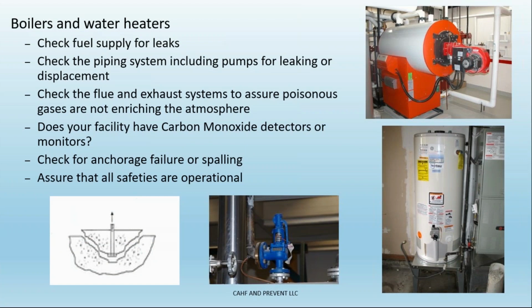Check your motor mounts on your pumps. Those are very important because they're independent from the water tank but could cause a major issue. Check your boilers and water heaters, looking at your fuel supplies for any kind of leaks, your piping system, including the pumps, any kind of displacement in one way or another. Check your flue and exhaust systems.